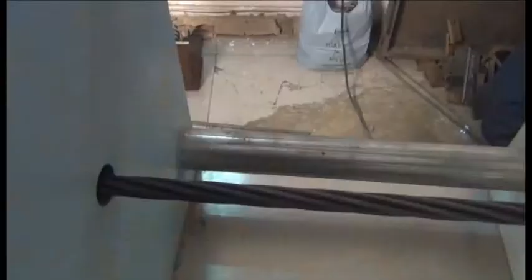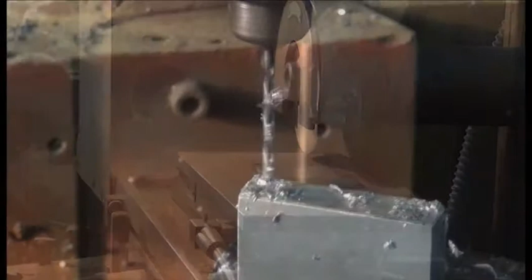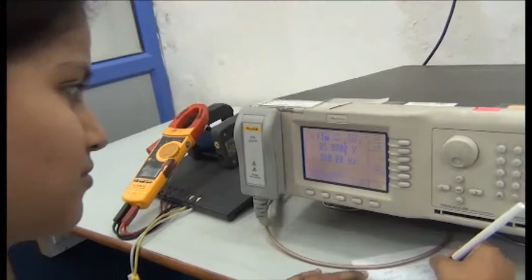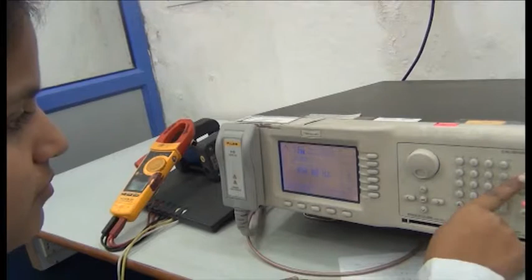The programming of the instruments is carried out by using programmable logic controllers and other related automation software, which are specialties of the group. One of the group's strong points is the design of quality systems for inspection, with the aim of developing robust industrial equipment capable of automatically performing quality control and validation of the product. This helps us to reduce the cost while at the same time guaranteeing product quality. This involves the calibration of the sensors being used, testing of the material used for the mechanical designing of the instrument including hydraulic testing of the pipes, and inspection of the endurance of the raw material as well as the finished goods and accessories.